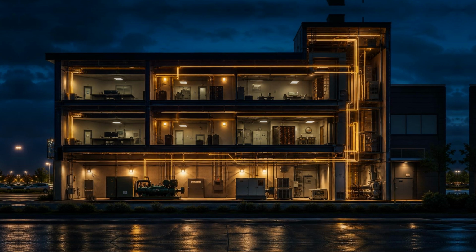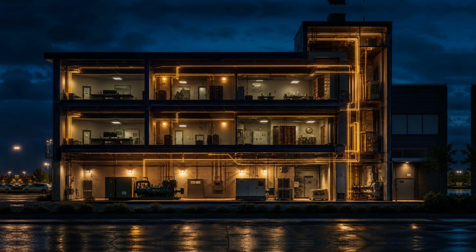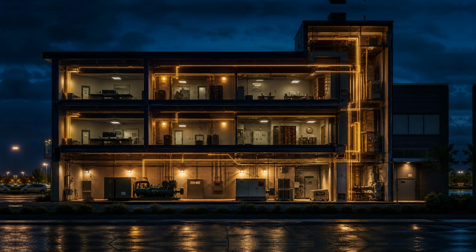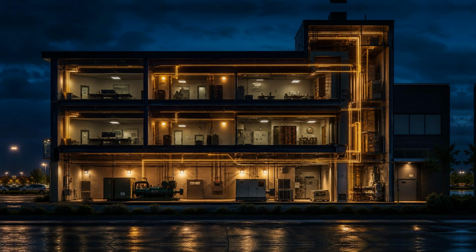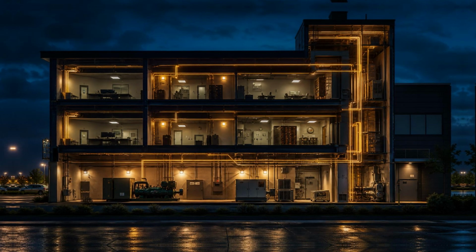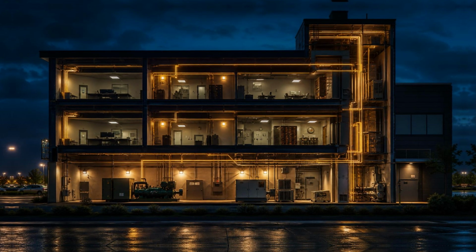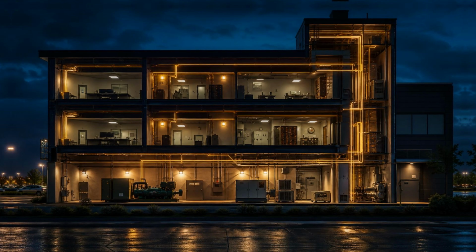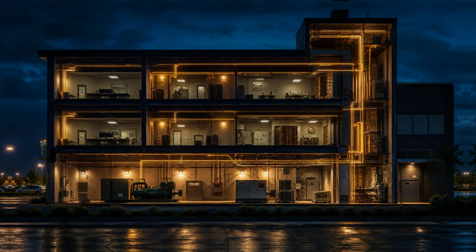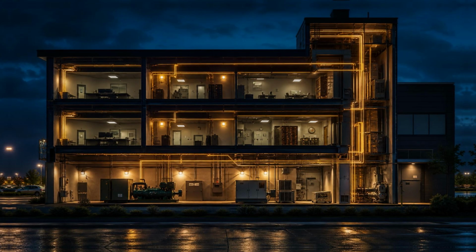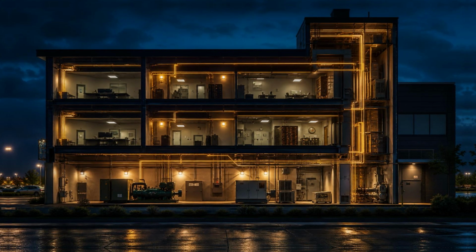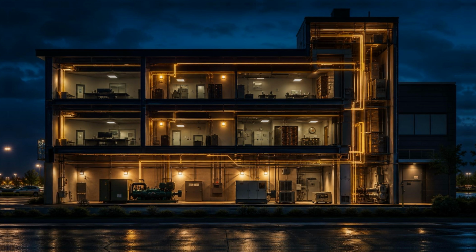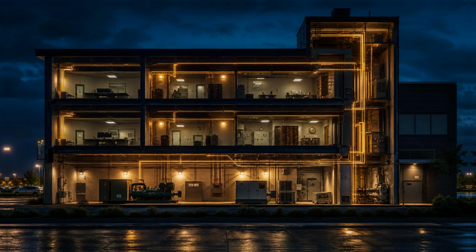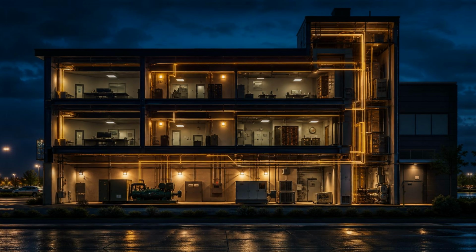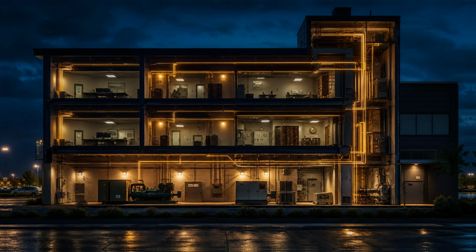This is why fuel management is a real and recurring part of emergency power maintenance. Fuel is sampled on a schedule, drawn from the tank and tested for clarity, water content, microbial contamination, and other indicators of degradation. Fuel polishing systems, recirculating filtration equipment that draws fuel from the tank, passes it through fine filters, and returns it cleaned and clarified, are used in some installations to maintain fuel quality continuously rather than simply monitoring it and reacting. Fuel stabilizing additives are used in others.